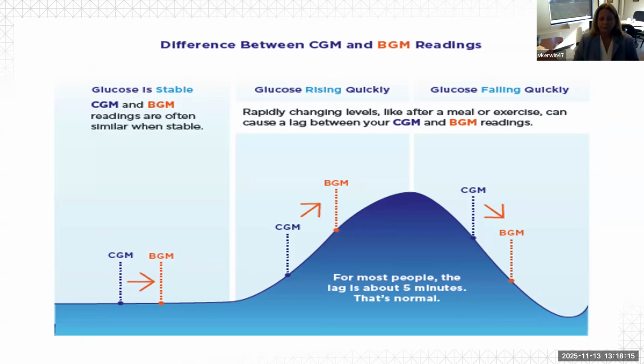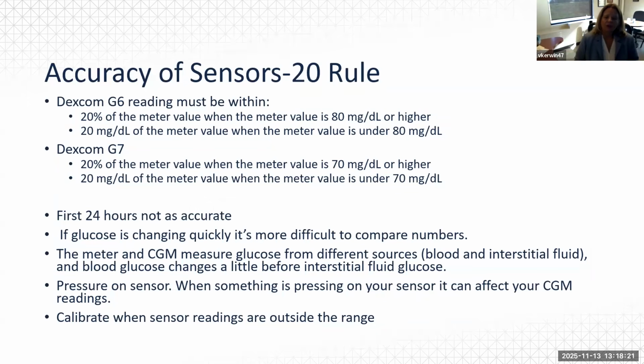Next slide. So there is the accuracy of these sensors. It's called the 20 rule. Let's look at the Dexcom G7. It says if it's above 70, there can be a 20% difference between a finger stick and a sensor reading. If it's below 70, you can have a 20 milligram difference. Remember I said with Dexcom, you can do a calibration. So if somebody has a wider variance between the two readings, they can calibrate their sensor and it will readjust. So it's the 20 rule. Again, make sure patients realize that a finger stick and a CGM are not going to be exactly the same. Also, it's a good idea to let people know the first 24 hours may not be as accurate. So if you're dosing insulin or medications based on a blood sugar reading off the sensor, you may want them to do a finger stick, okay?